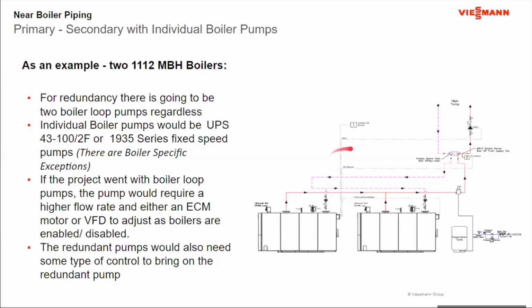Now also, and I'm going to go in the generic case. In the generic case, these pumps here also can be single speed pumps. Now I don't have to go variable flow on my secondary because my primary is going variable flow. I can go fixed flow here. And by doing fixed flow as a reference point, if I'm doing 2 1 million BTU boilers, these pumps are going to be fixed speed pumps. For example, a UPS 43 100 Grundfos might be the choice, or a Taco 1935 series pump could be the pump of choice. So it's a smaller, less costly fixed speed pump in most cases.